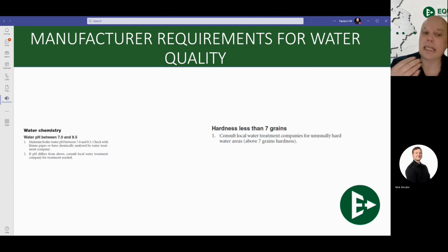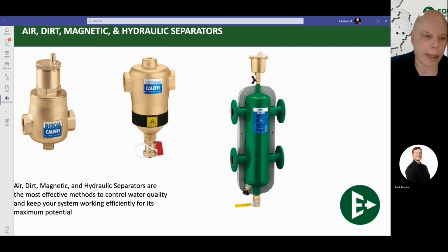So it is important. Read that, make sure you understand that, make sure the contractor, the homeowner, the builder understands that as well. That shows that you're not just charging an additional $20 to $100 for whatever reason. There's a reason you're doing this, because it has to be installation manual compliant. Then we get into our trim. There are a couple pieces of trim required by code. The only piece that is literally written down that is required is your high efficiency air separators. A high efficiency air separator is required by code, the CSA B214.